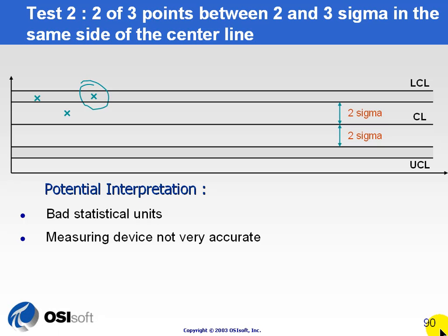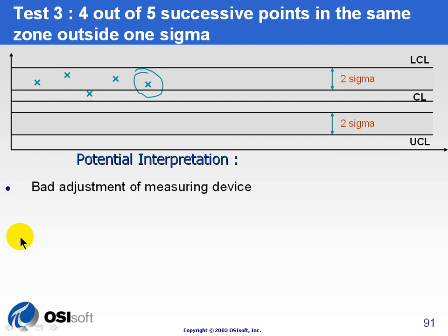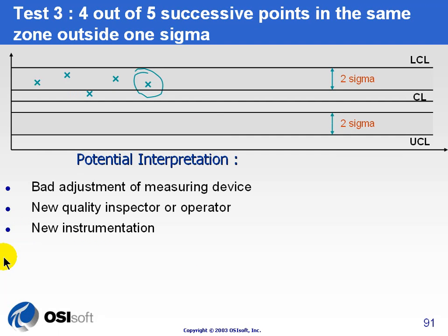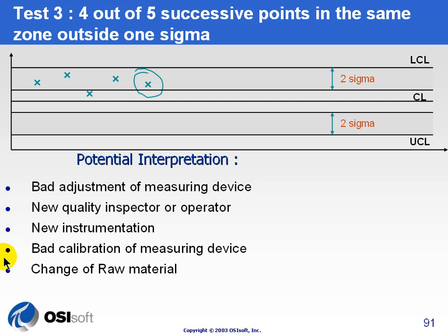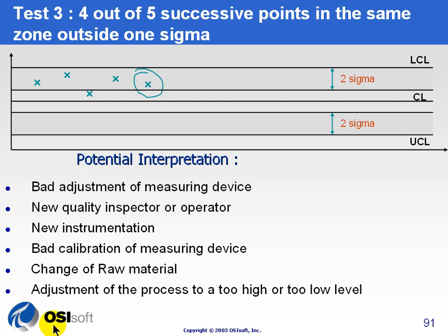As you go through the list of different Western Electric tests, you'll notice that many of them involve either bad fundamental assumptions on your data when you created the alarm limits, or measuring devices that are becoming inaccurate. Things come up fairly routine, but you'll find some new ideas — for example, perhaps there's been a change in raw material. In test three, four out of five successive points in the same zone would be an indication that the material being measured is just not the material you think you're measuring. It could also be an adjustment of the process to too high or too low a level — somebody's changed a set point, so it's fundamentally running the process a little differently, which means your SQC alarms are no longer within the right range.